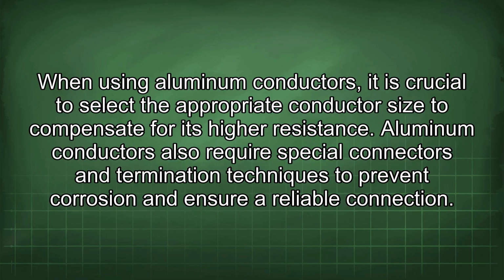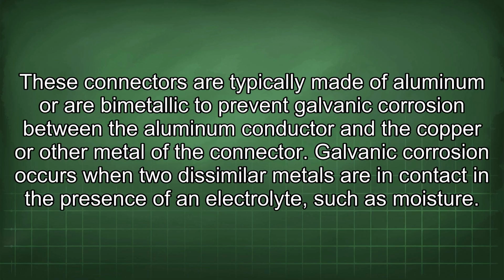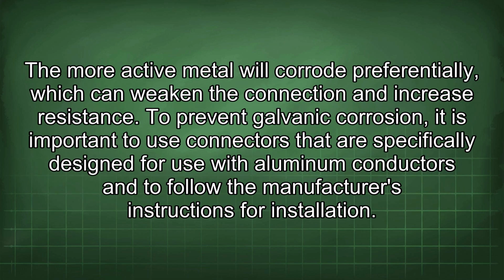high resistance. Aluminum conductors also require special connectors and termination techniques to prevent corrosion and ensure a reliable connection. These connectors are typically made of aluminum or are bimetallic to prevent galvanic corrosion between the aluminum conductor and the copper or other metal of the connector. Galvanic corrosion occurs when two dissimilar metals are in contact in the presence of an electrolyte, such as moisture. The more active metal will corrode preferentially, which can weaken the connection and increase resistance.